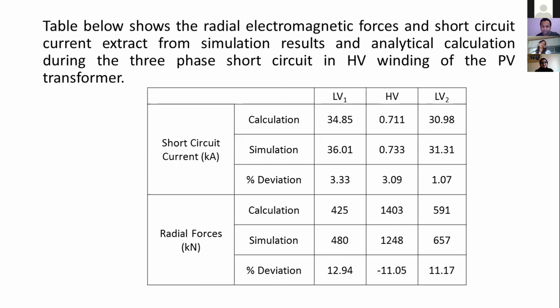In this table, the comparison of the radial electromagnetic forces and short circuit current between the simulation and calculation result is given. According to the results, the short circuit current in the inner LV winding is about 34 kiloampere, where it is 36 kiloampere extracted from the simulation result, and the difference between the analytical and simulation or numerical result is about 3% for the inner low voltage winding.